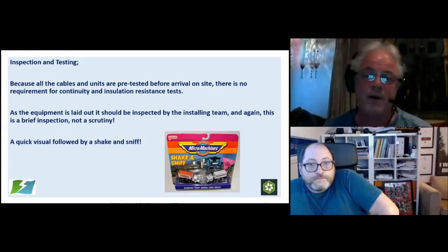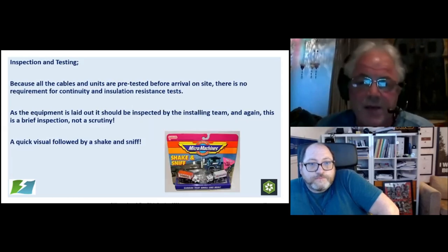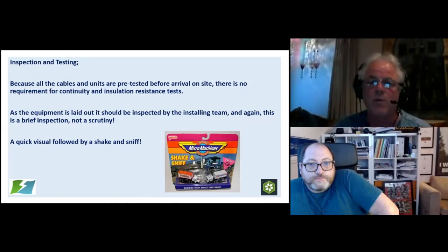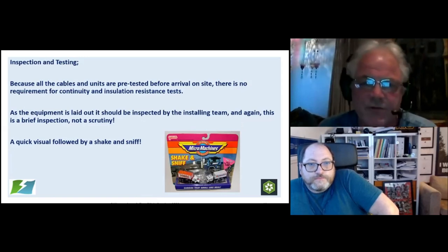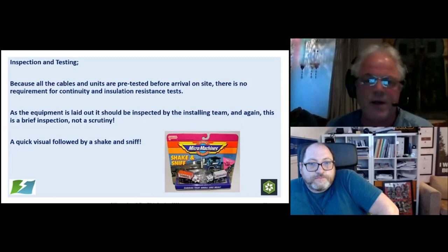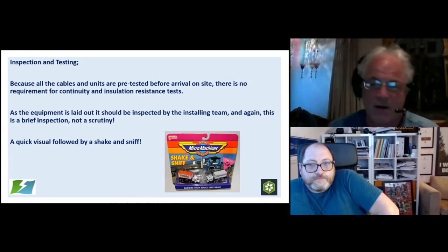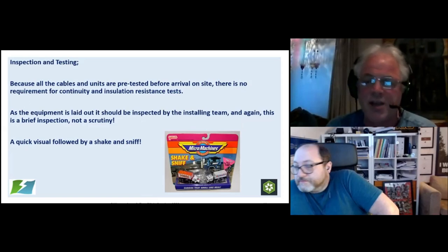As we said, because all this stuff is pre-tested, pre-inspected before it arrives on site, there is no requirement for a continuity test or insulation resistance test. That's all done prior to its arriving. When we lay out the equipment, I get guys to do what I call a shake and sniff. Yeah, so as you're laying out extension leads.